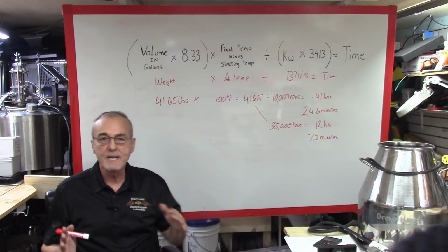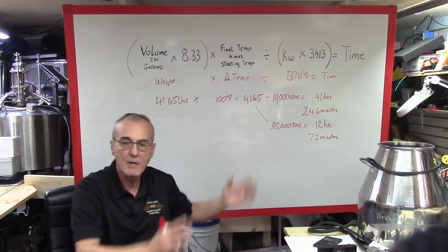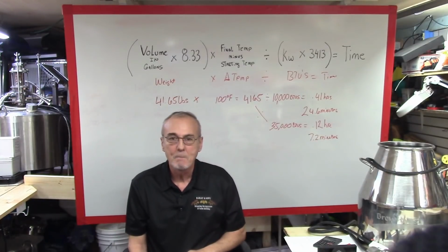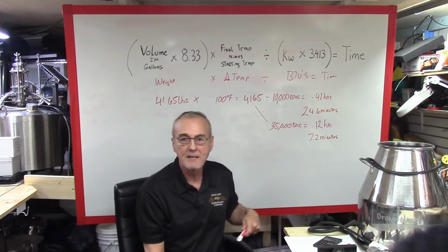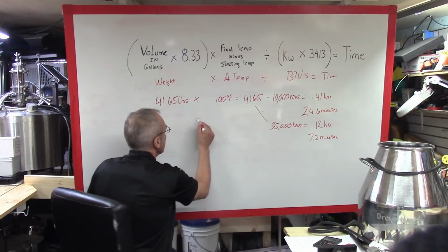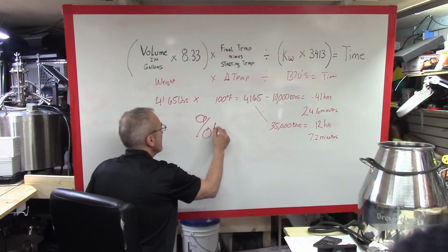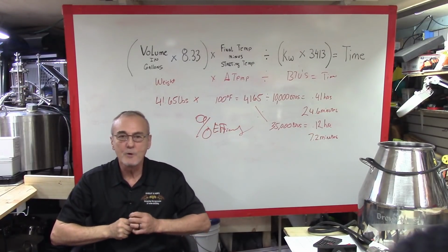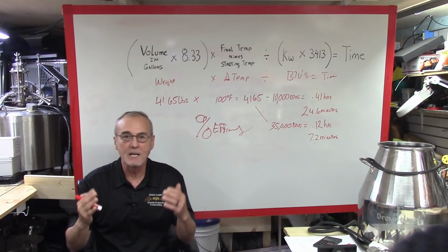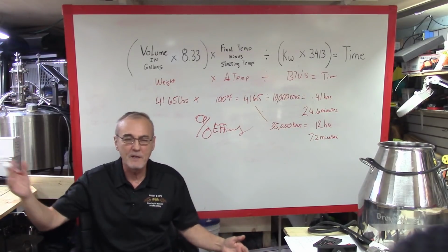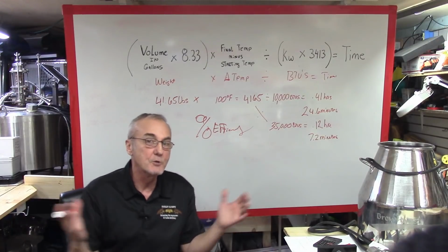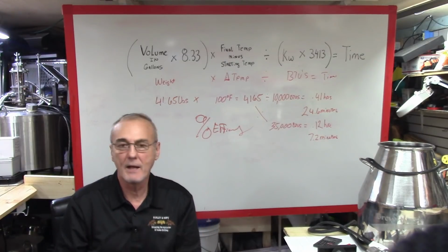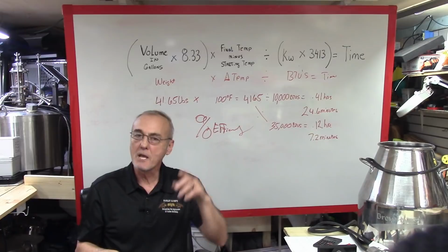Now remember, this always negates the potential heat loss. But also remember that if you know how long it should take, and you divide that by how long it does take, that's going to tell you your percentage of efficiency of your system. So you'll have a data point and an understanding of your system completely from start to finish, because all you're trying to do, again, is to control the amount of heat loss and where that takes place. That heat loss should take place at your condenser.